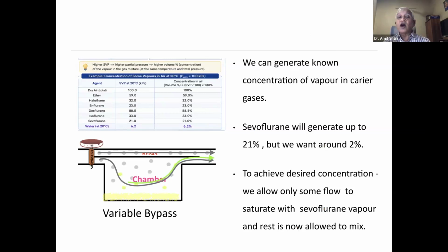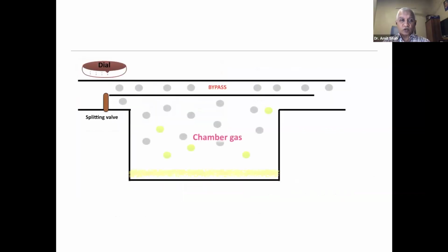variable bypass. So if you have heard the word variable bypass, the reason to have a variable bypass is that sevoflurane generates a very high concentration of vapor, and we want only a smaller concentration of vapor. So we allow only a small part of that particular gas to pass through. How does it work? A carrier gas routinely passes through here. Suppose we switch the dial to say 1%, what will happen? A splitting valve, this is a splitting valve, will open up and allow some gas to pass through the vaporizer chamber.